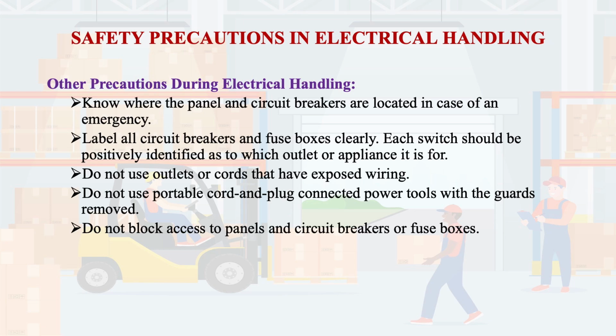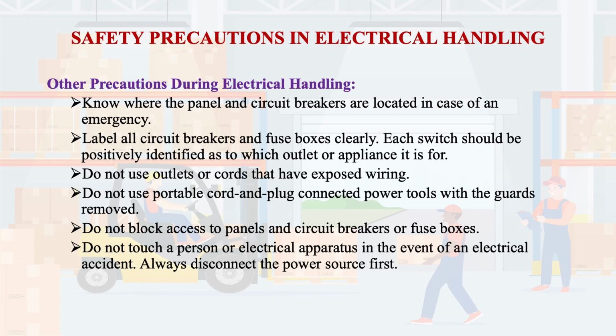Normally, contractors remove the guards in the company, and some workers also have the habit of removing the guard for their own ease, but this is a very serious safety violation. Do not block access to panels and circuit breakers or fuse boxes. Do not touch a person or electric apparatus in the event of an electrical accident. Always disconnect the power source first. Then you move for first aid or taking the person into the open air.